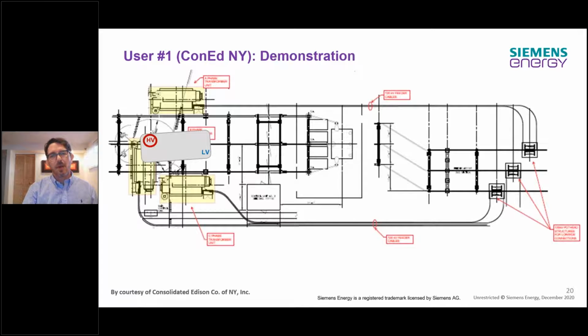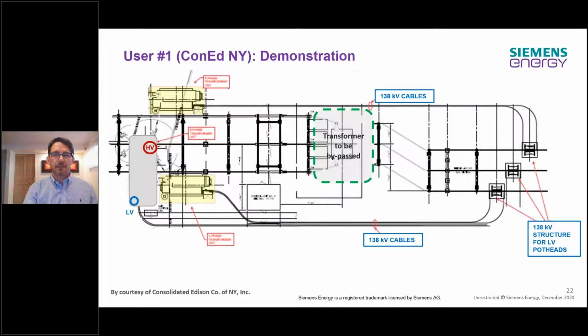One of the nice things about having the combination of cables and bushings is that you can rotate your transformers in many ways and put them in places you normally wouldn't be able to. So this is the final arrangement that was decided by Con Edison. You see on the left the three resiliency units, with high voltage bushings installed, but the low voltage using cables. You can see the cables running around the unit that needed bypassing.